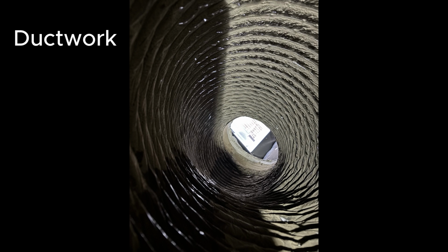And the blower motor is kind of the king of this realm, because the blower motor is what creates the negative pressure that sucks air in from the home to go across the evaporator coil and remove heat that way. And it also creates the positive pushing force that pushes the cold supply air out of the supply vents throughout the different rooms in your house. So the blower motor is what controls both of those forces, the sucking in and the pushing out. And just be aware that you have ductwork in your home of some sort.